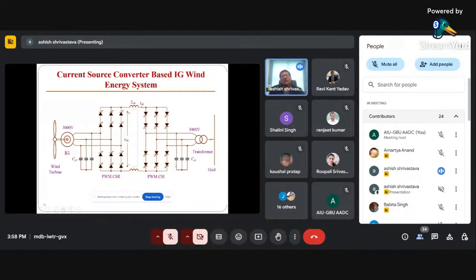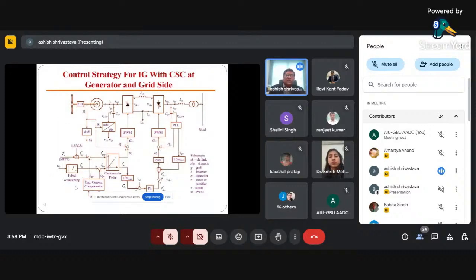And again, on the other side, you are connecting the capacitor for reactive power compensation. So this is how you can control. But since these are all controlled devices, IGBTs, you need to provide the pulse at the gate terminal, for which you require a control algorithm or control strategy, which is the most important part. So this is one of the control strategies for the current source converter on one side.